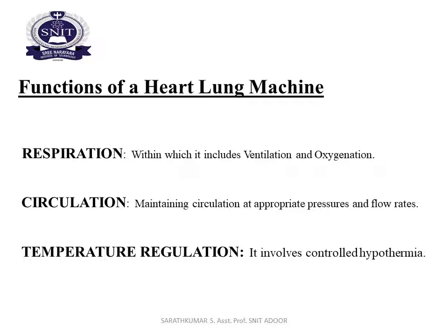There are three main functions of a heart lung machine: respiration, circulation, and temperature regulation. Respiration includes both ventilation and oxygenation. Circulation involves maintaining blood flow at appropriate pressures and flow rates. Temperature regulation involves controlled hypothermia — lowering the body temperature — to protect the patient during surgery.